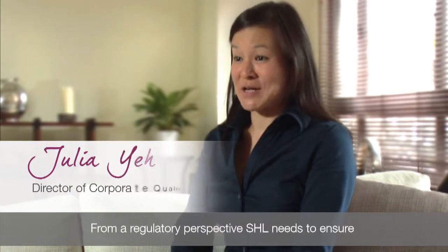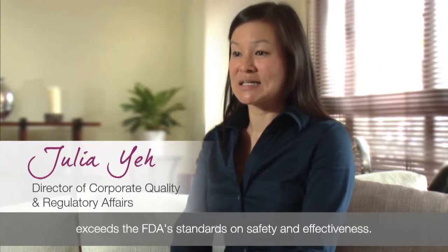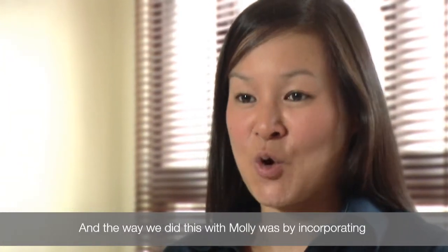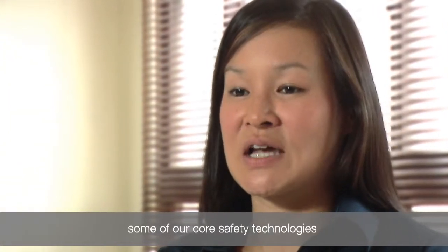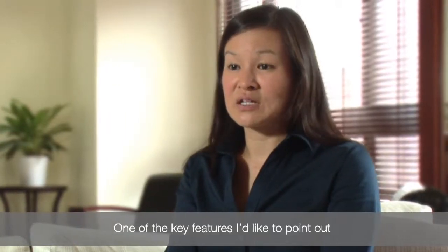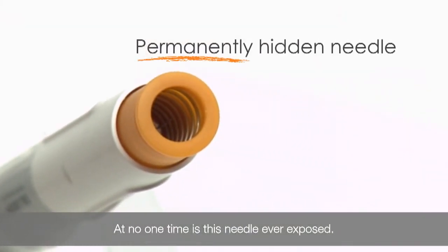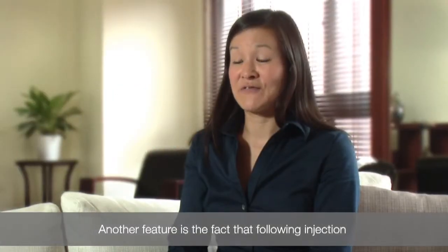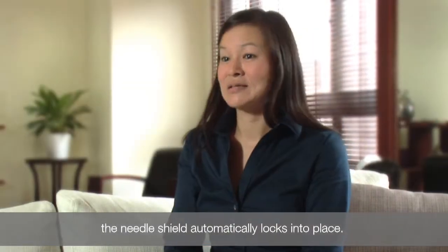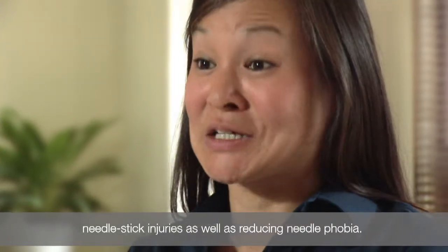From a regulatory perspective, SHL needs to ensure that every device we submit for 510k clearance exceeds FDA's standards on safety and effectiveness. The way we did this with Molly was by incorporating some of our core safety technologies from proven devices we currently have on the market. One of the key features is the permanently hidden needle — at no point is this needle ever exposed. Another feature is that following injection, the needle shield automatically locks into place. These features are critical because they prevent needle stick injuries as well as reducing needle phobia.